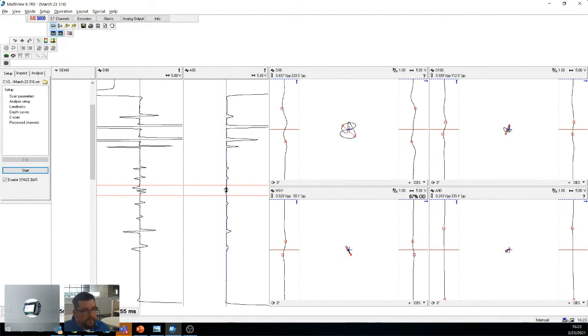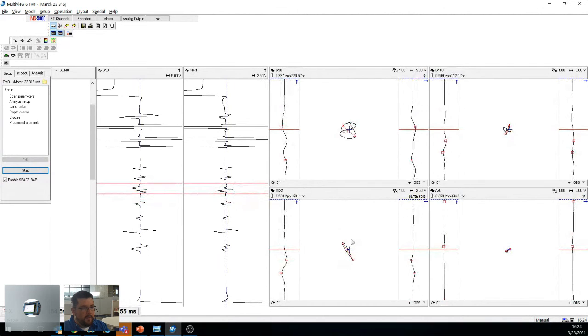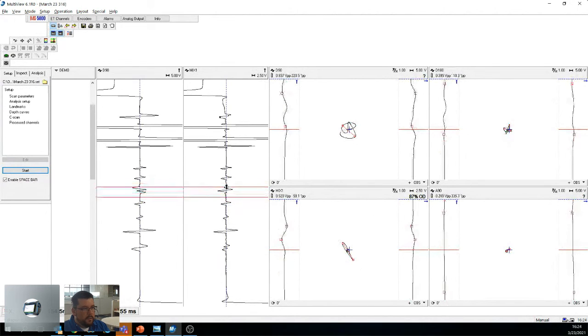However, there is a bit of a return to the center nominal wall in the middle. So there is something counterbalancing the support. But right now, I really can't see. So all I do is go on the mix channel, which is right here, and I'll zoom in a bit. On the mix, it actually sees the defect pretty well. Yes, there's a bit of noise left from the support, but overall, you're getting a good idea of what's going on.